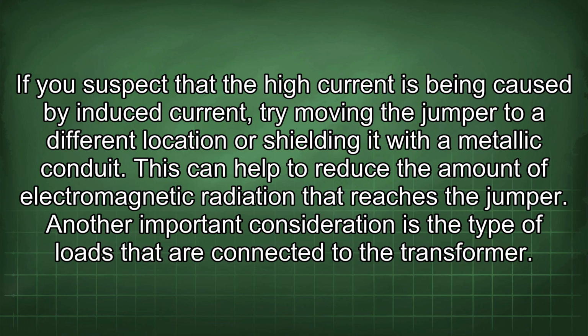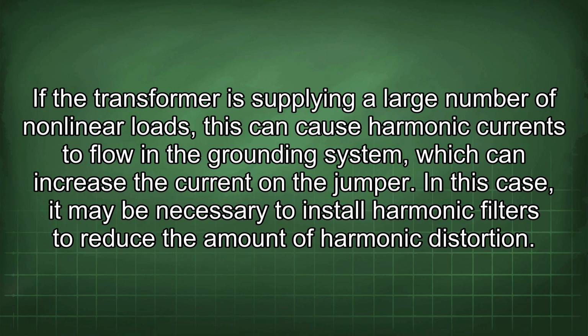Another important consideration is the type of loads that are connected to the transformer. If the transformer is supplying a large number of nonlinear loads, this can cause harmonic currents to flow in the grounding system, which can increase the current in the jumper. In this case, it may be necessary to install harmonic filters to reduce the amount of harmonic distortion.